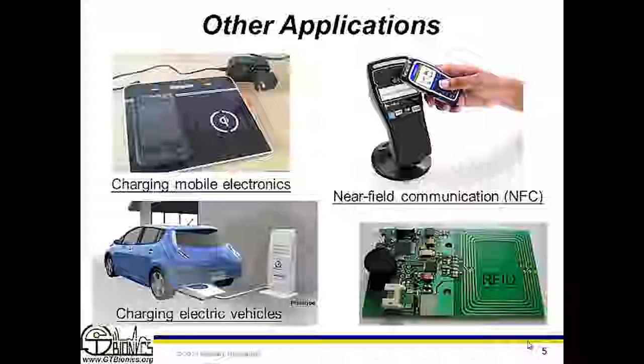I will present some of the fundamentals of inductive coupling. Just before I go further, a little bit more about the choice of frequency, because the temperature rise is very important, and one thing I did not mention is that the choice of frequency does affect the temperature rise. Why? Because depending on what frequency you use for your inductive power and data transfer, the rate of absorption in the body, which is more than 90% water, is going to be totally different.